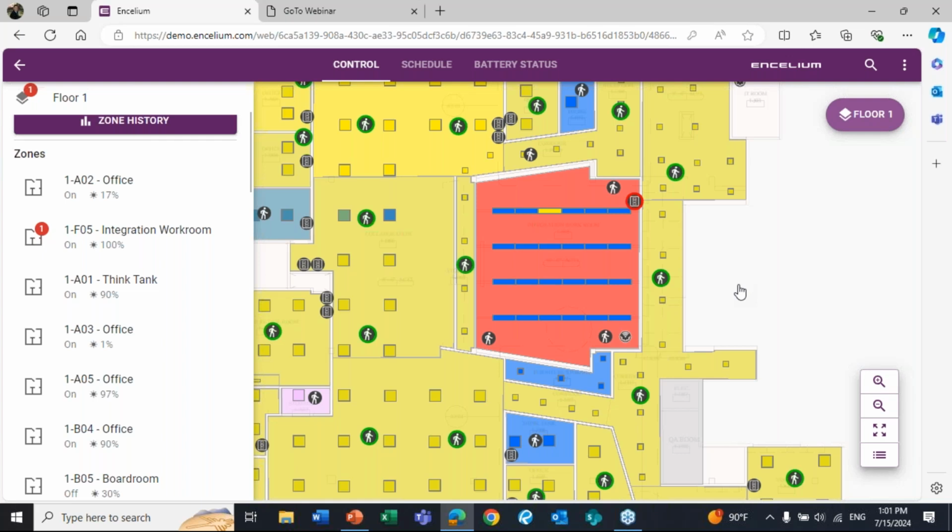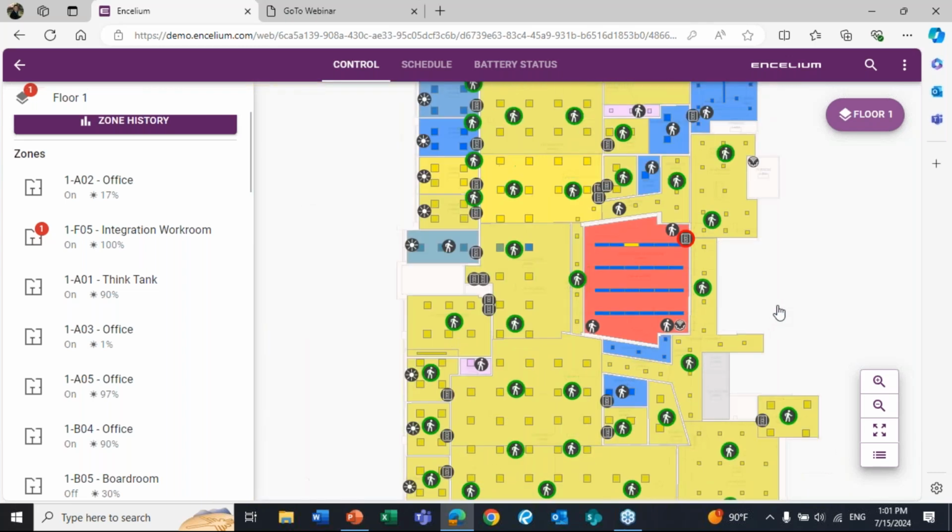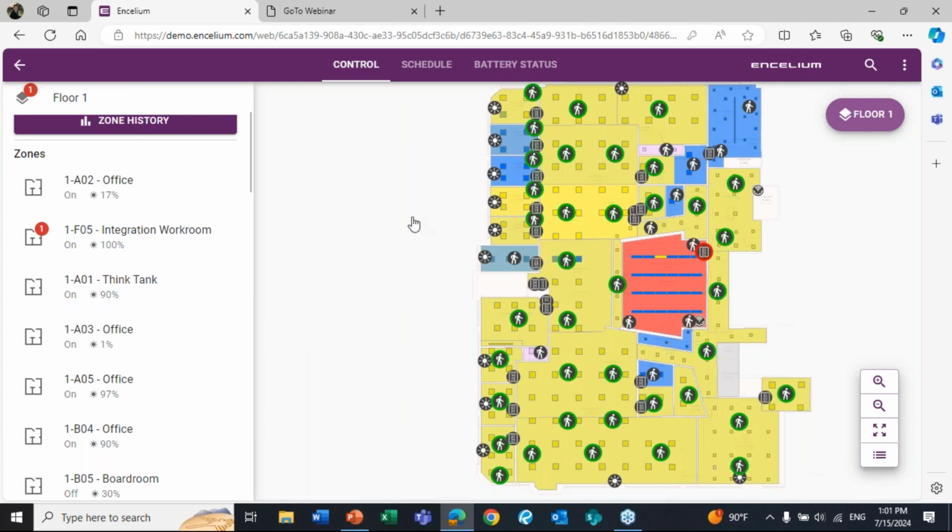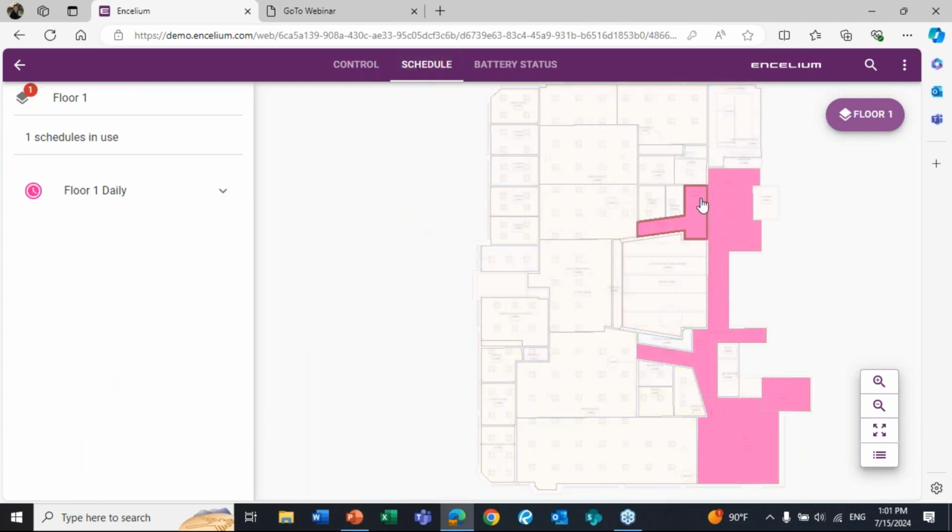At 9:01, time schedule has expired, and then the occupancy sensors, because we actually have the hardware in this particular space, will actually kick in and start controlling the lights. And that's reflected in all of those reports. So again, being able to see where your time schedules are by space.